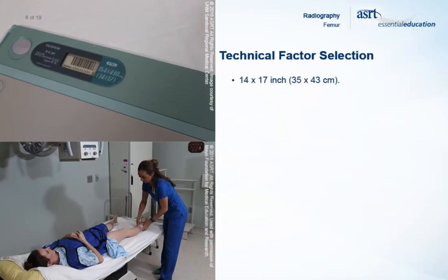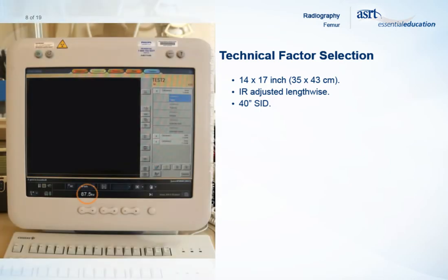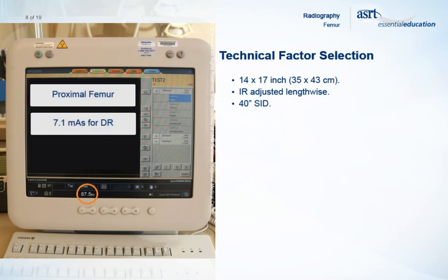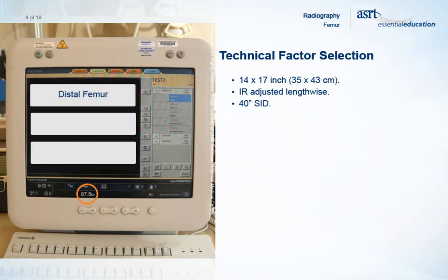A 14 by 17 inch or 35 by 43 centimeter image receptor is used for an AP projection of the femur and is adjusted lengthwise. The SID is set at a minimum of 40 inches, although some departments may require a longer SID. Collimation is adjusted to 1 inch or 2.5 centimeters on both sides of the leg and remains at 17 inches or 43 centimeters in length. 87.5 kVp is a common setting for AP projections, and generally a grid is used. Automatic exposure control may be used to achieve the proper mAs setting. However, common mAs settings for a proximal femur projection are 7.1 mAs when using digital radiography and 14 mAs when using computed radiography. Common settings for a distal femur projection are 3.6 mAs for digital radiography and 7.1 mAs for computed radiography. A small focal spot is selected with all settings.